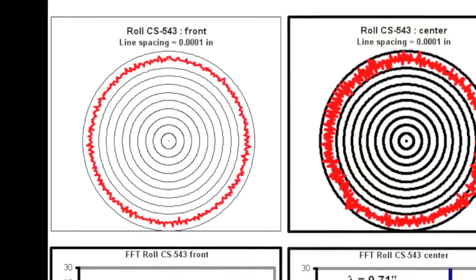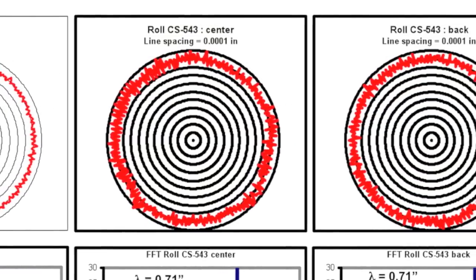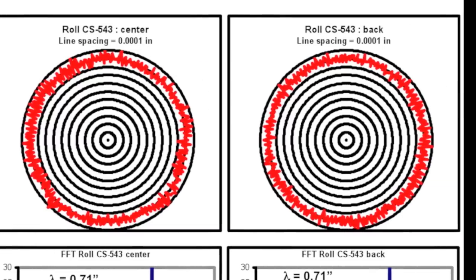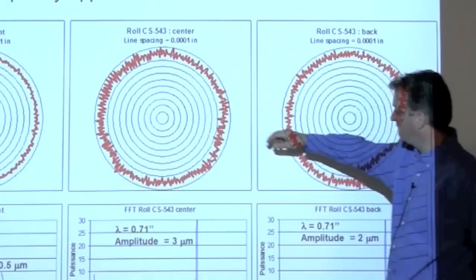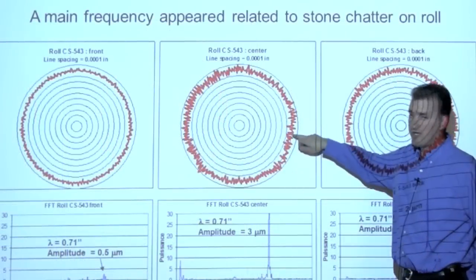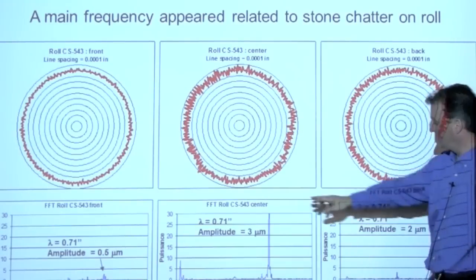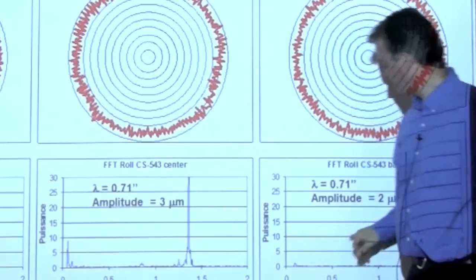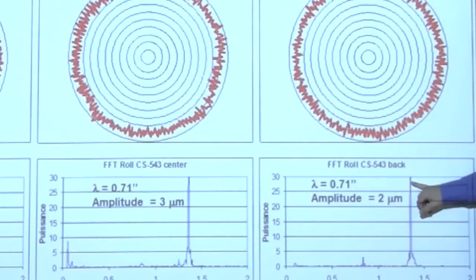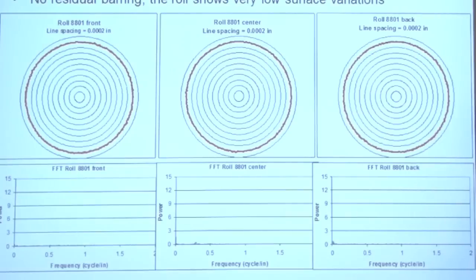This graph here shows the front, center, and back position of a calender roll after grinding, and we see some chatter at the surface of the roll — all those small bumps. When we completed a frequency analysis at the surface of these three-position rolls, we have the graphs for front, center, and back. We see there is a peak that appears, and this is a periodic event at the surface of the roll.